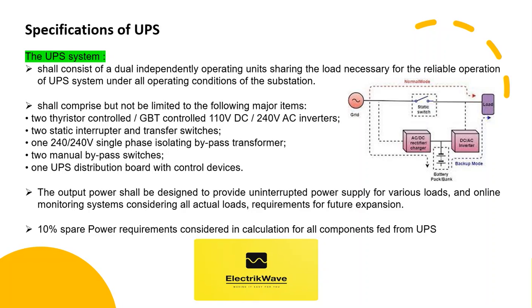The output power shall be designed to provide uninterrupted power supply for various loads and online monitoring systems, considering all actual load requirements for future expansion. A 10% spare power requirement may be considered in the calculation for all components fed from the UPS.